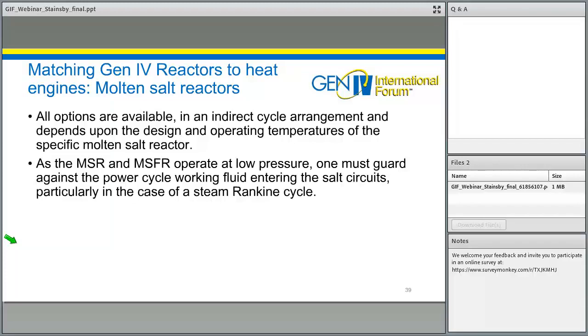All heat engine circuits will operate at higher pressures, so if you get a leak in one of the main heat exchangers, you'll get power conversion system fluids leaking into the salt circuits, which is not good. If water enters a molten salt circuit, you get severe corrosion issues. If gas leaks in, you get pressurization issues for the structure. So you might still need intermediate circuits in molten salt reactors to protect the fuel salts from being contaminated by working fluids from the power conversion system.